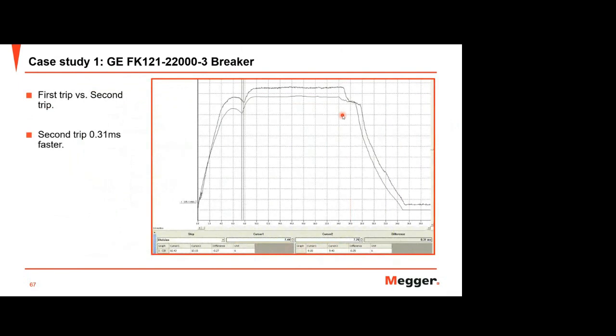So in general, first trip versus second trip: 0.31 millisecond faster compared to the first trip. This is the first trip, this is the second trip, faster. And first trip versus the third trip, again the timing improves and gets faster: the third trip is 0.66 millisecond faster. This actually happens when you do conventional testing: if you exercise the breaker more, it will affect the performance of your breaker. It looks like it gets better time by time.